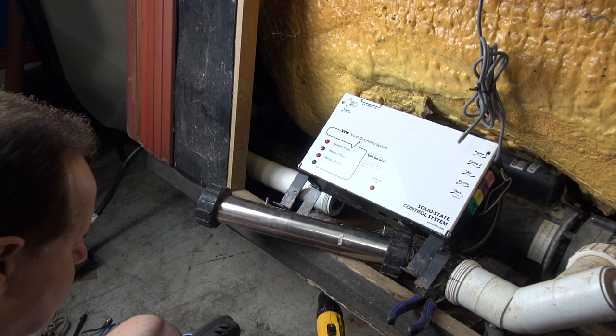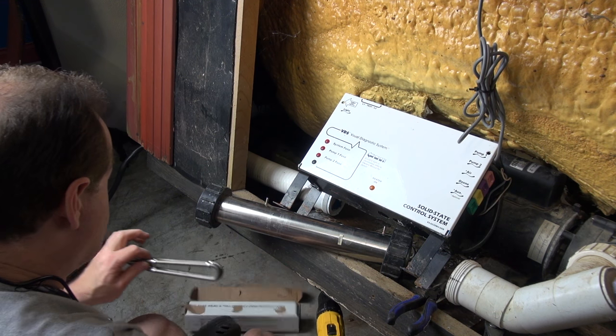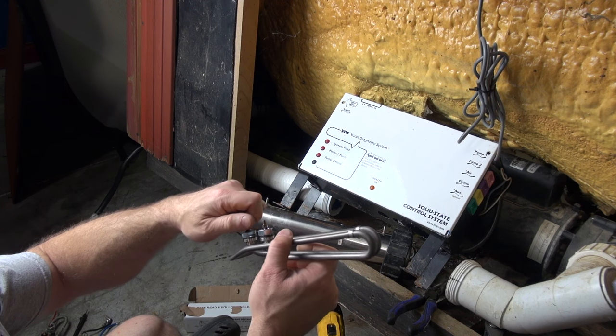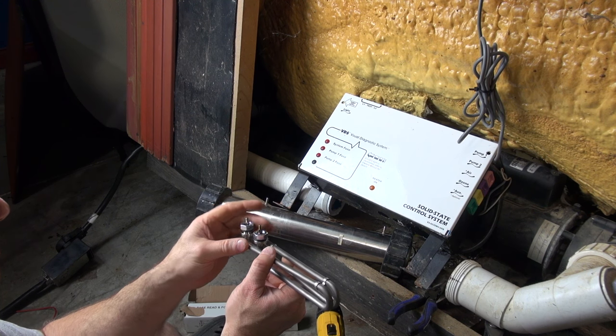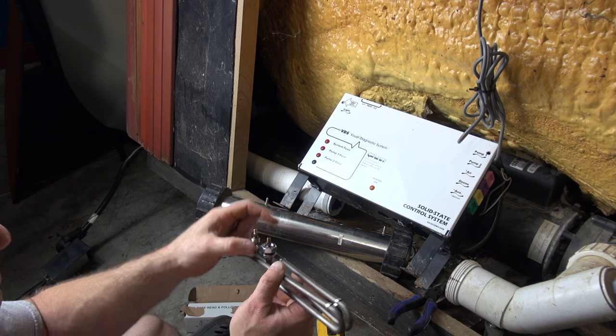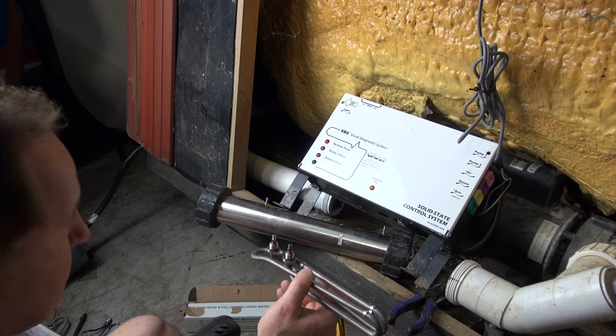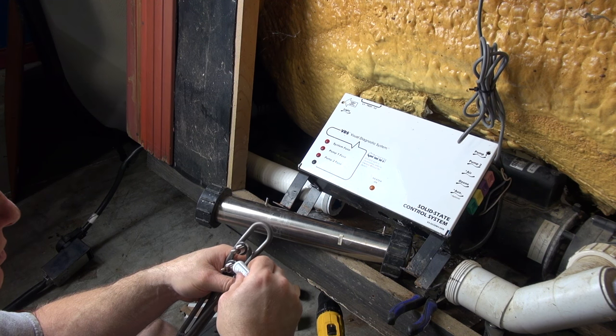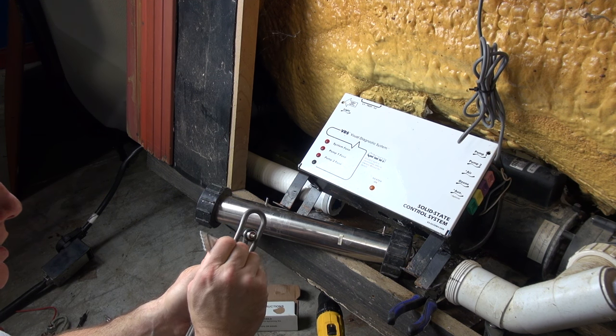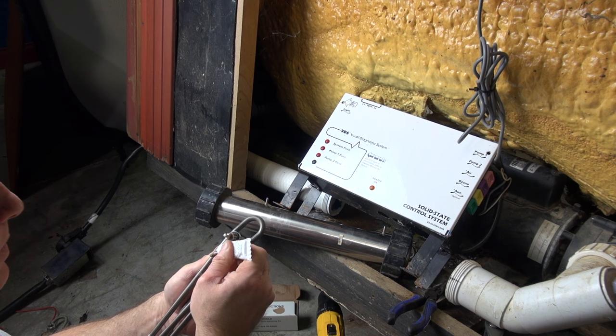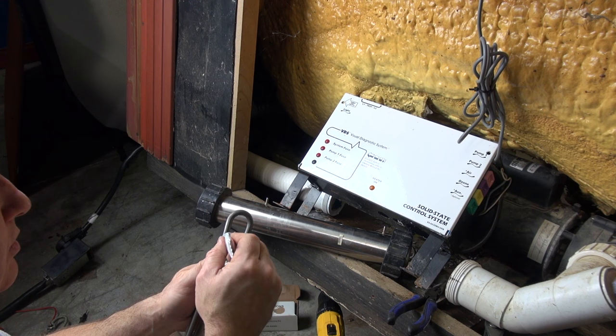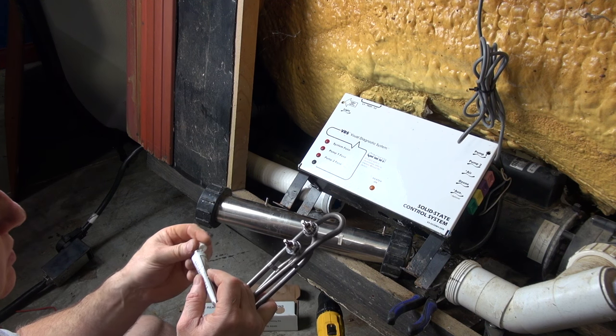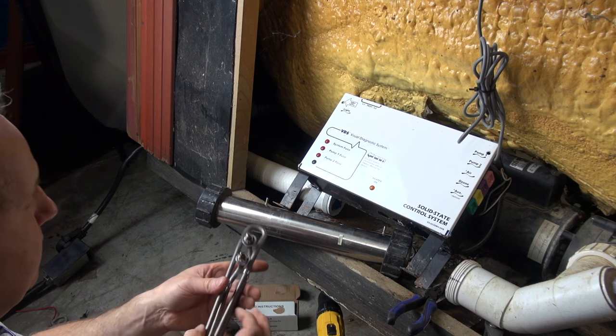So now what we're going to do is I'm going to go ahead and put the new heater element in. And I only use titanium now. I don't use the Incoloy or any of the other heaters. This is a little bit of insurance if you will. Now when you do this, and this is a titanium element, you can see there's a little O-ring under each one of these nuts. Now one thing that I do is we offer a kit that comes with some clear silicone. And what I like to do is, I don't put a whole lot on it but you need a little bit of silicone around the threads. What will happen is if you don't seal it up that water can walk the threads and it can actually walk the threads and trip the breaker as well. So if you seal it up, it does a couple of things. It keeps the nuts from backing off from vibration and it also ensures a good seal.